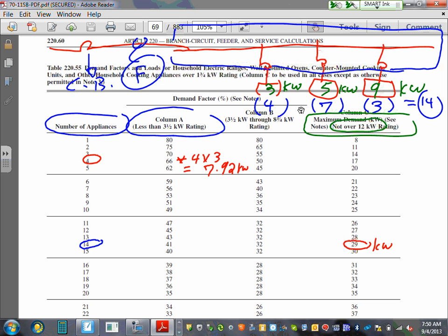The 5 kW. How many of the 5 kW do I have, Adam? 7 of them. So I'm going to go all the way to 7. And under 7, this is my derating factor. Remember, that was my derating. You guys multiply the 0.66. These are percentage times. I have 7 of them, so 7 times 5. So do me a favor. Can you get me 40% times 7? 14? Thank you. 14 kW.